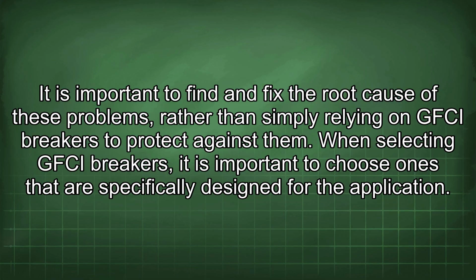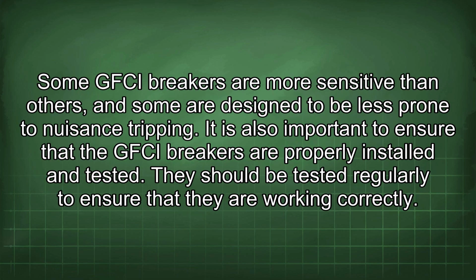When selecting GFCI breakers, it is important to choose ones that are specifically designed for the application. Some GFCI breakers are more sensitive than others, and some are designed to be less prone to nuisance tripping. It is also important to ensure that the GFCI breakers are properly installed and tested. They should be tested regularly to ensure that they are working correctly.